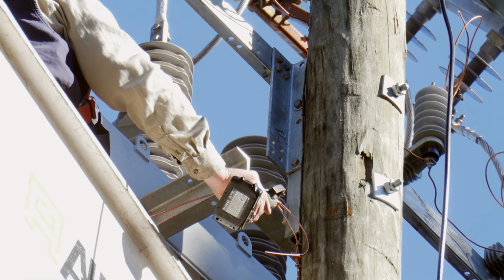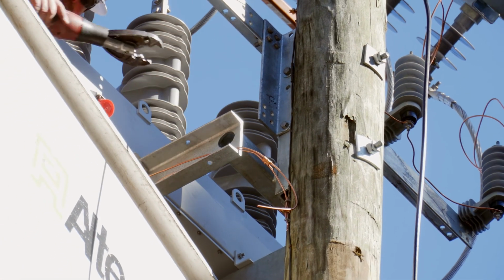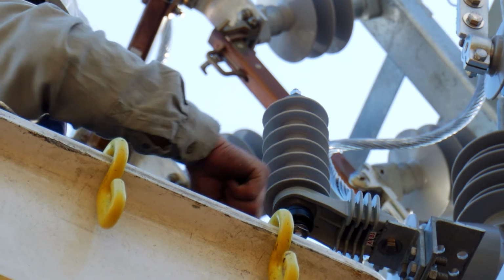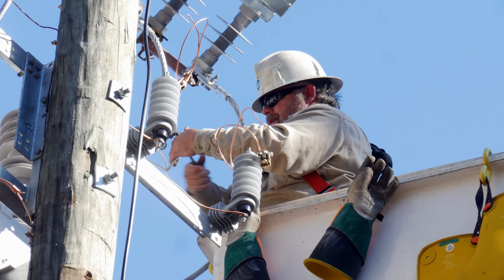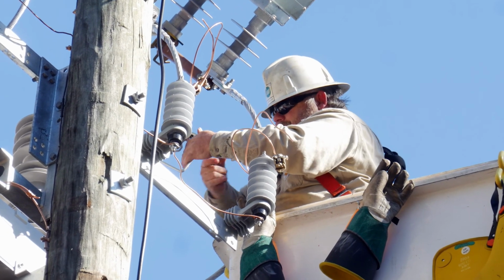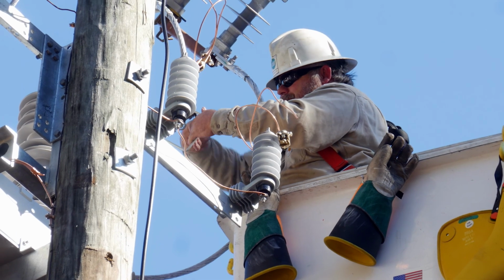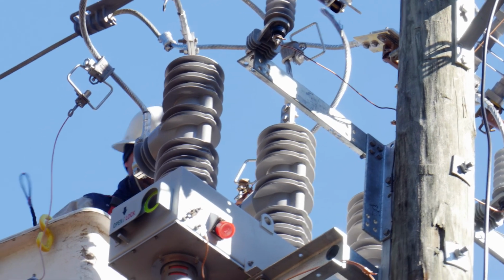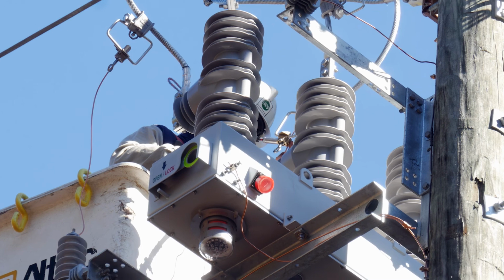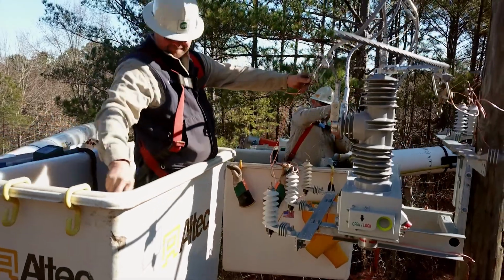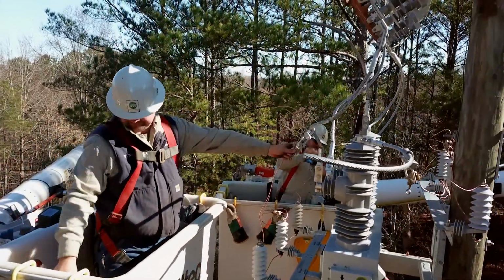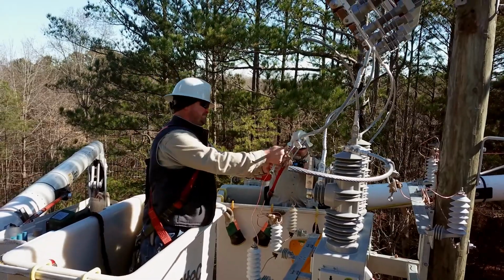With solid grounding lugs on the recloser mounting bracket, as well as the recloser itself, utility crews can quickly move from grounding to then attaching the arrestors to the high voltage lines via jumpers. While there are a variety of ways to do this, this utility utilizes hot line clamps to attach the arrestors to each incoming and outgoing jumper.